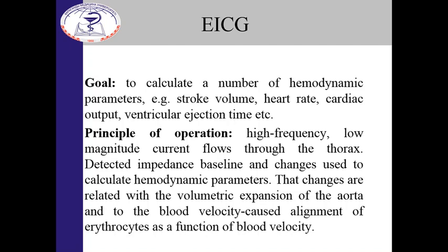We put the electrodes above the thorax, on the neck, and on the lower part of the thorax. And we measure the overall impedance of this part of the human body. And we assume that this impedance will change over time in a rather rapid way. But what could be the reason for such rapid changes? It's definitely the pumping activity of the heart.